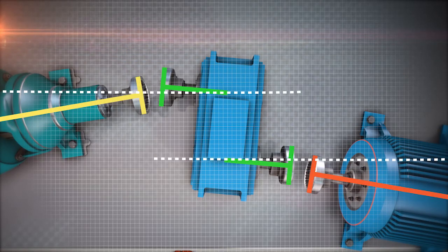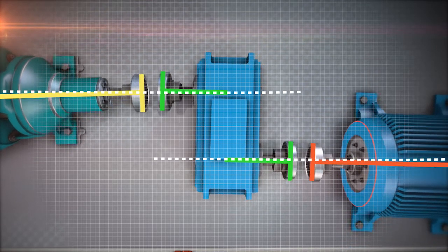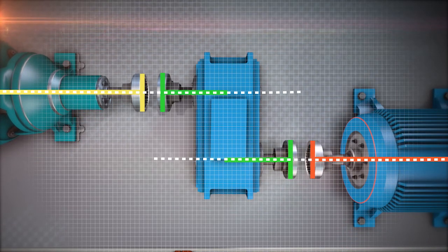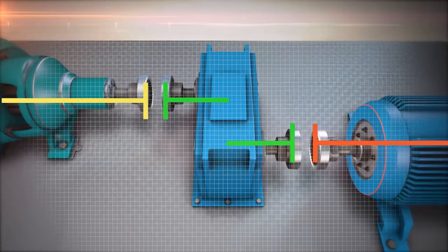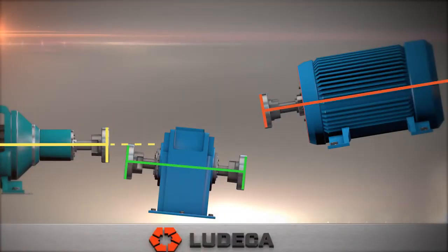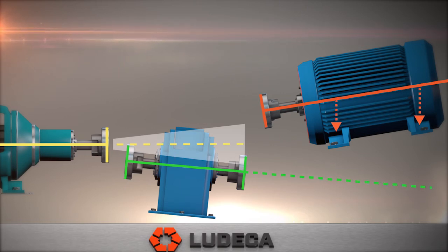Once we know the misalignment between the machines, we can plan on making the smallest correction possible across the machine train. A common example is when the end machine is considered the reference machine. Notice that the back of the motor needs a large adjustment to be aligned.